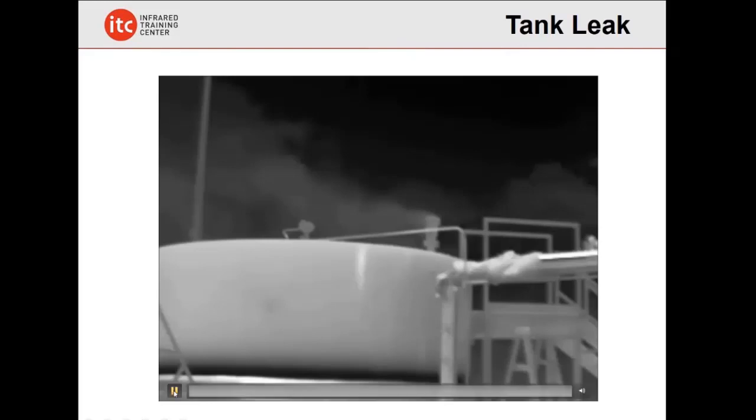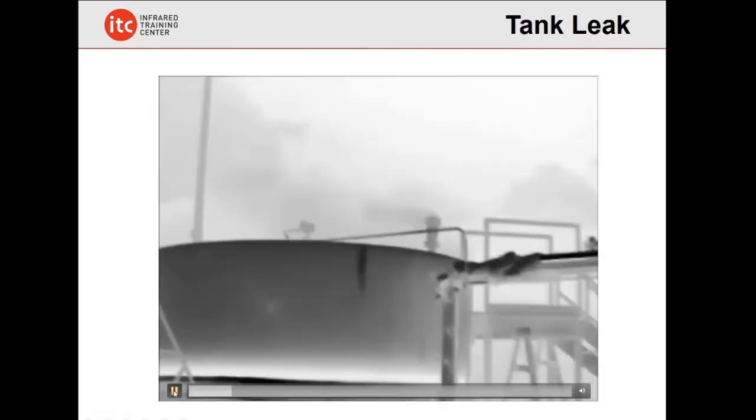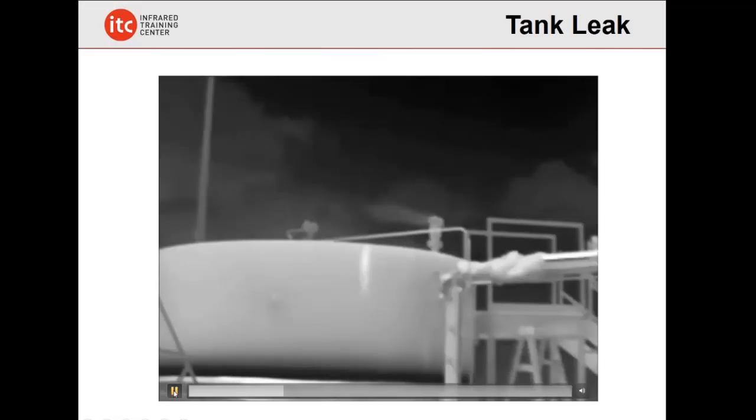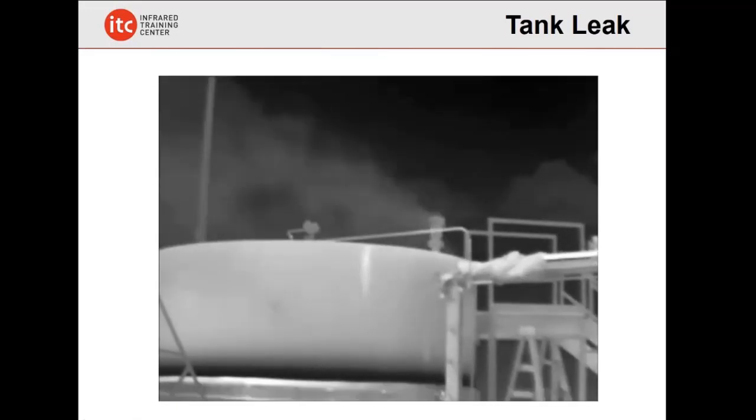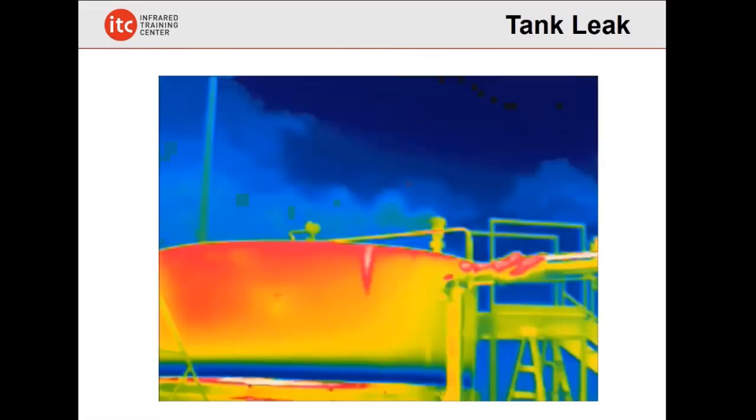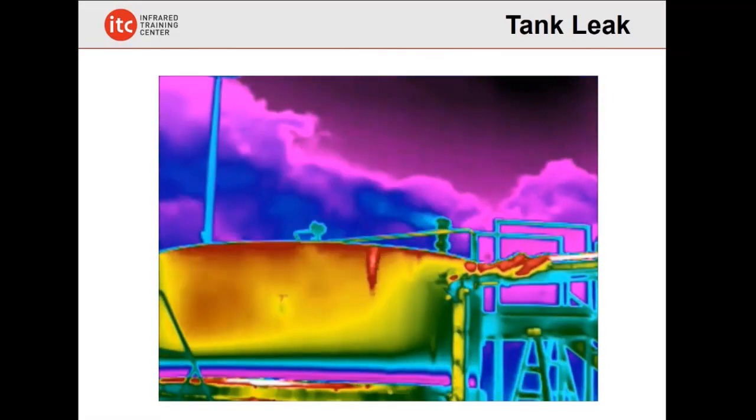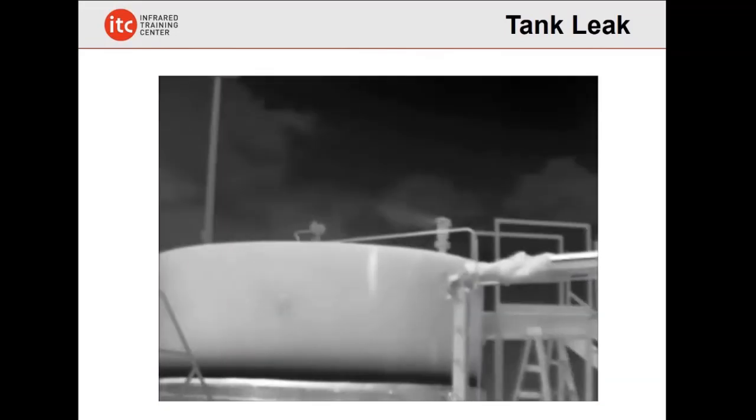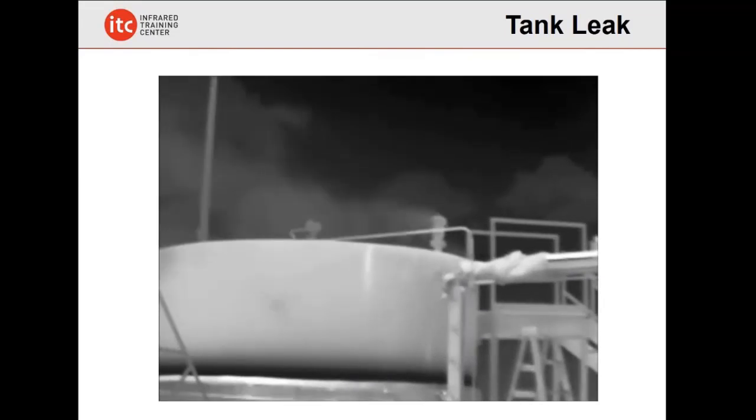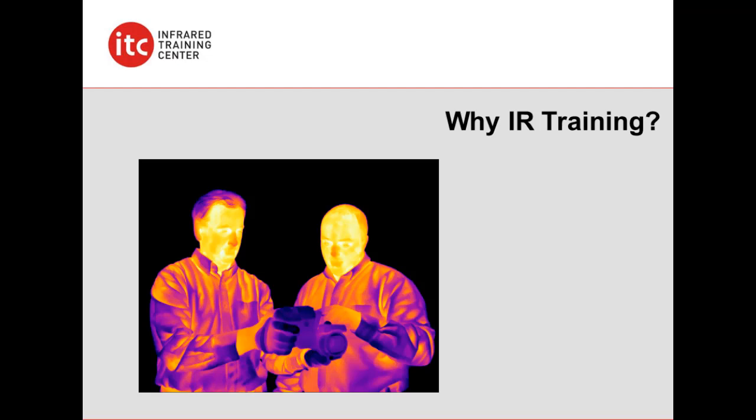There's also gas detection. Most of which are mid-wave thermal imagers, can actually detect a variety of different gases. In this case here, hydrocarbons like propane, hexane, butane, which don't show up visually, can't be seen with a naked eye, but thermally we can detect this due to the nature of the gas and how it responds thermally in a very specific mid-wave length of infrared. A great application here, optical gas imaging, that we, in fact, actually have another webinar available on as well.